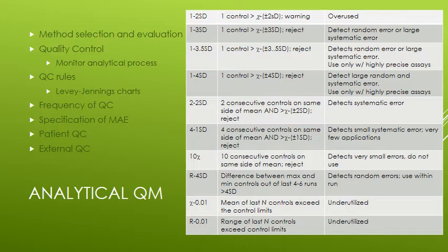So it has to be everything from where it's going to fit in the lab to how it actually runs, so you're getting good results for your patient population. Once you have all that information, then in stage 2, you're going to start branching out a little bit, and you try to determine day-to-day imprecisions that might occur. So this helps you to establish what kind of daily QC needs to be run.